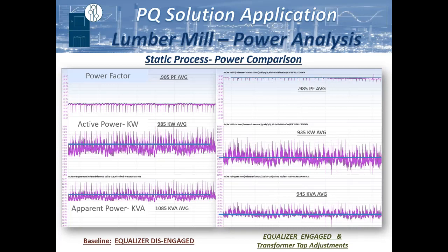Well, oftentimes, instead of having to add a new service, a new transformer, which could cost $3.5 million, like we've had several projects lately where they either had to add a new transformer, which is $3.5 million, or they can install several small units all throughout the facility to optimize their capacity being used. And instead they installed 10 systems for $350,000, all said and done, and they had more than enough capacity without having to add additional capability on their service or a new transformer. So that can be a huge cost savings or cost avoidance measure that could be beneficial.